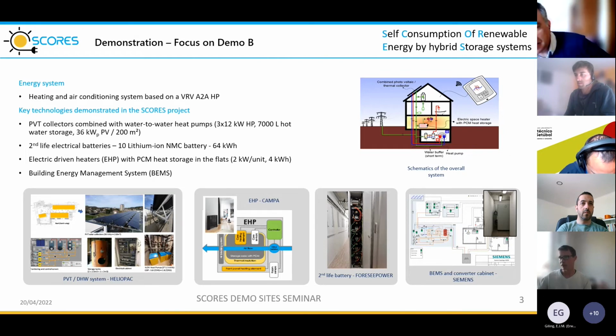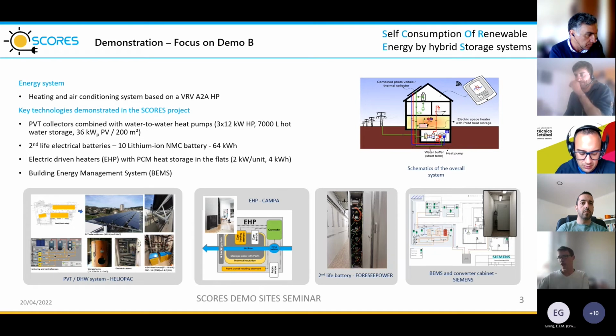A PVT collector for supplying domestic hot water, connected to a water heat pump - 3 times 12 kilowatts of heat pump - with 7,000 liters of hot water storage, coupled with 36 kilowatt peak of PVT, roughly 200 square meters.